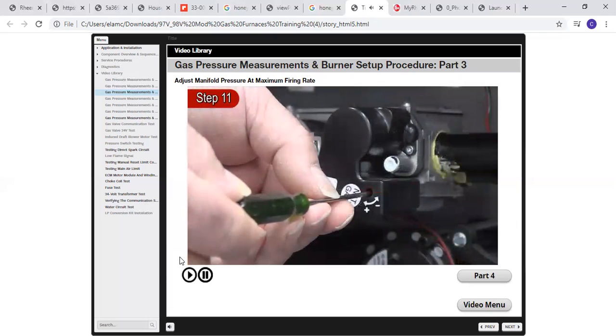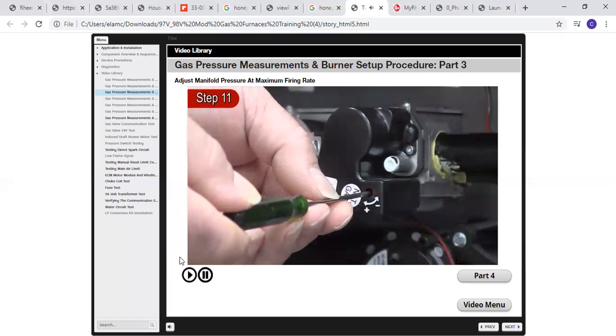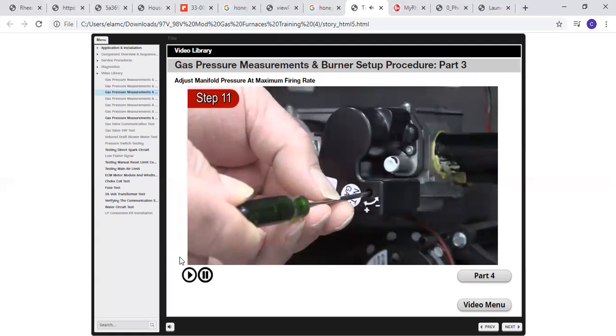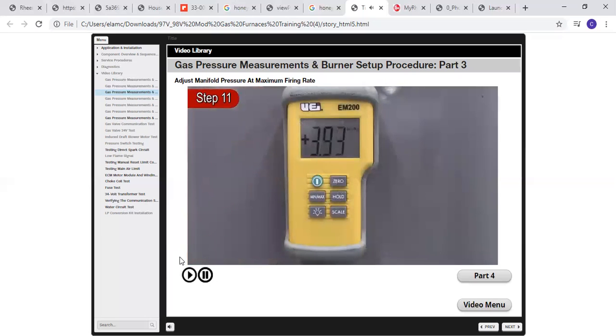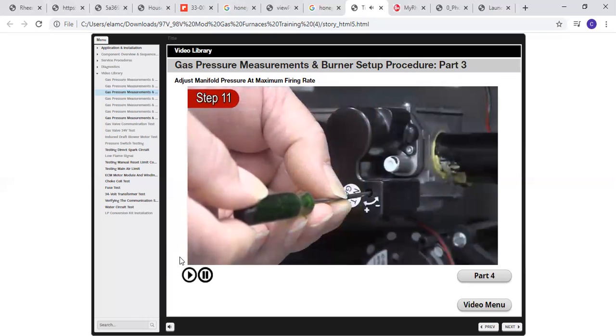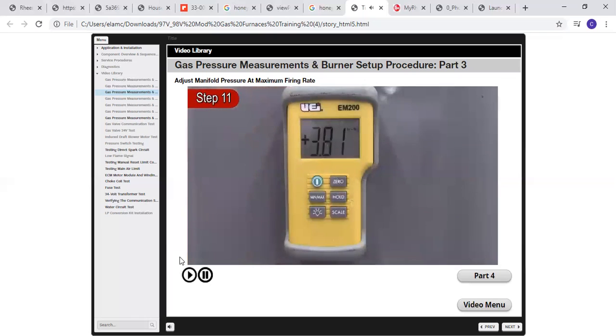The adjustment wheel will not stop rotating when the valve outlet pressure reaches its maximum or minimum value. Instead, the wheel can be rotated further, but no further adjustment of the outlet pressure will be made. Once the maximum adjustment, high or low, is reached, the wheel can be turned in the opposite direction, and this will cause the pressure to also move in the opposite direction. The first click in the opposite direction will cause a pressure change in the opposite direction, even if the maximum adjustment in the other direction was exceeded by several clicks.